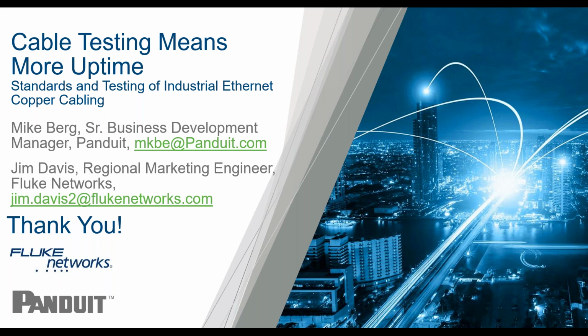Yep, so I can talk to that, and Jim, if you want to, you can talk to it as well. On that slide, we were showing the shielded cabling. Of course, when you get to that E3 level, fiber optic devices and cabling could obviously have application to mitigate that noise level, and that is done in certain applications using the fiber connection. So that's a great point. I think the PON might actually be the plastic optical networks. The availability of product and devices at this level is not as strong, so you're going to have a lot of copper need, a lot of copper-based devices at this level of network where you need to address the noise factors.